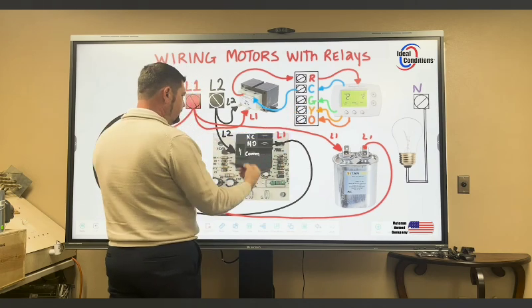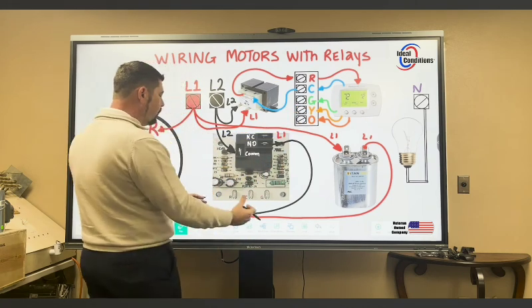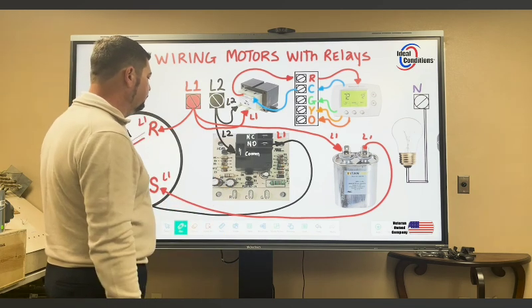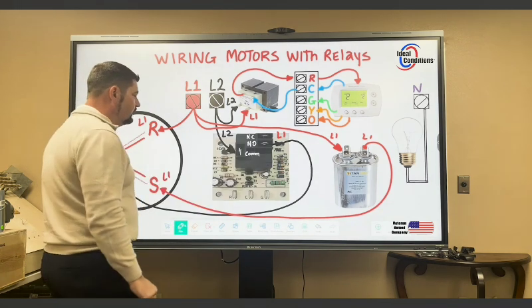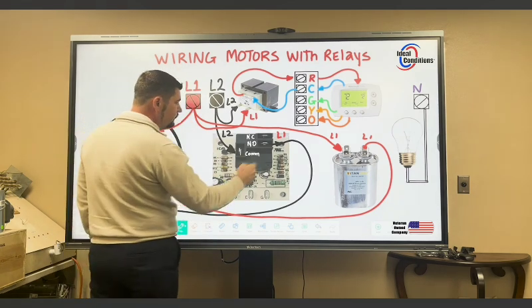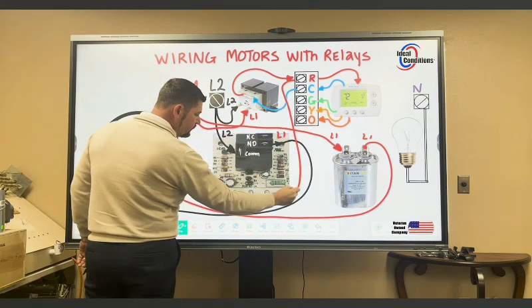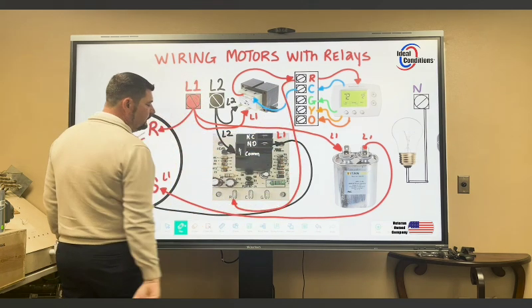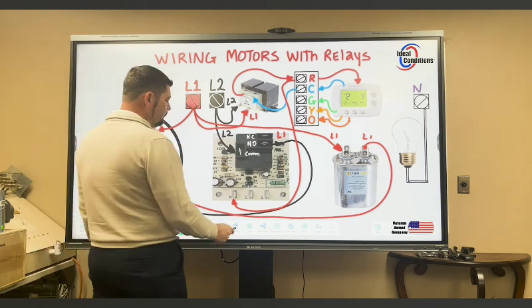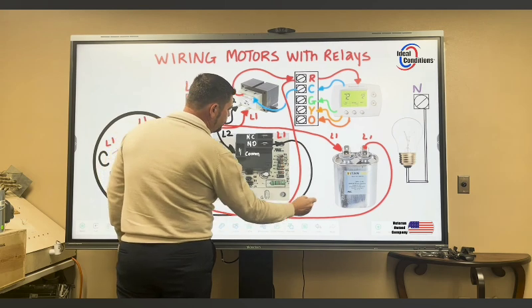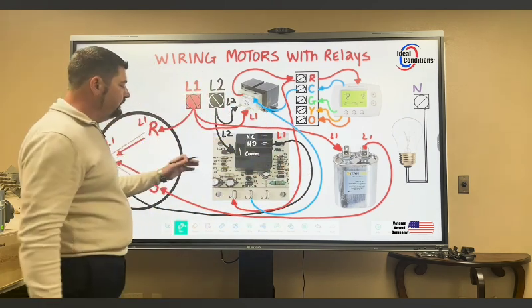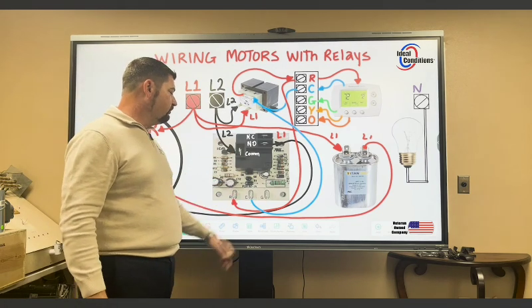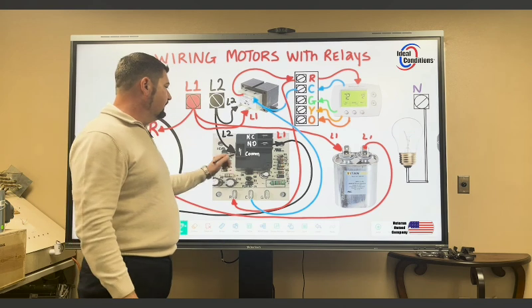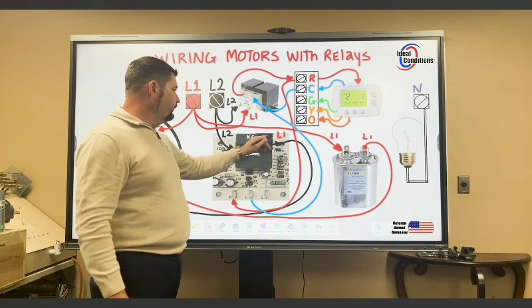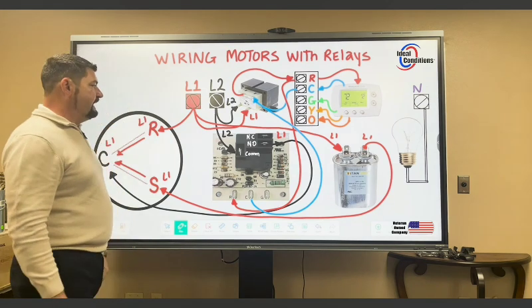outputs. So when I take that G call, I'm going to apply it to the board, but this board is a working load. It needs 24 volts at all times. So it's not going to work without having the call for red at all times. So how we do that is we're going to come down here from the terminal block, and we're going to land 24 volts input on the blower control board. We're going to come out of the blower control board, back over to the transformer, and now the board is on standby. It is ready to receive 24 volts, and the moment it loses that G call, it's going to hang out and provide L2 right here for a 50-second countdown on an off cycle.